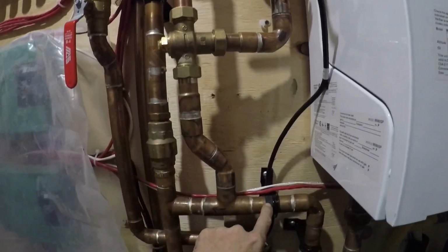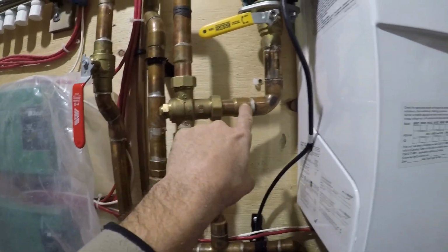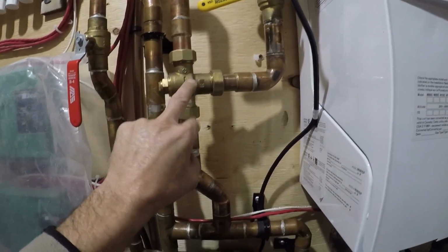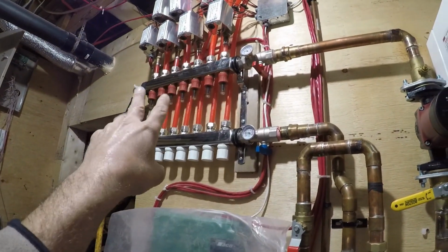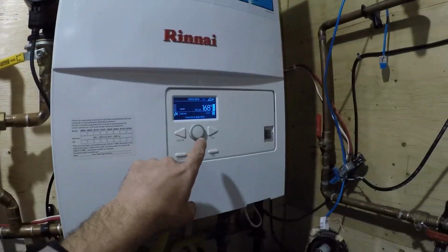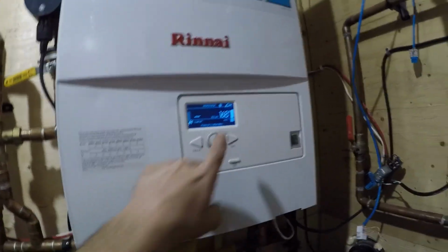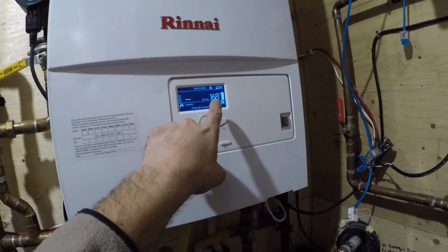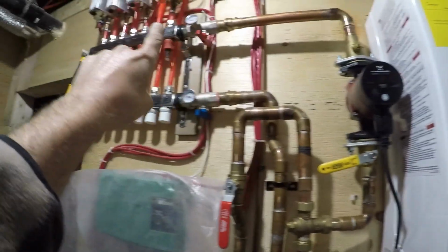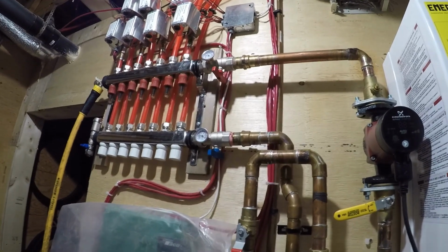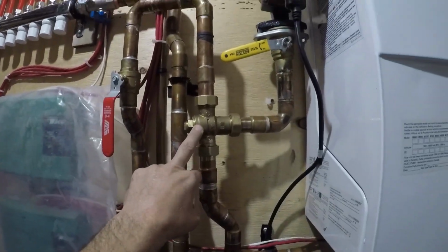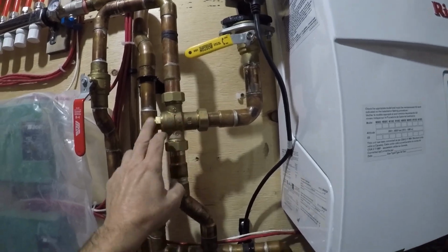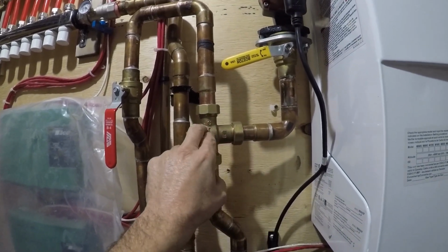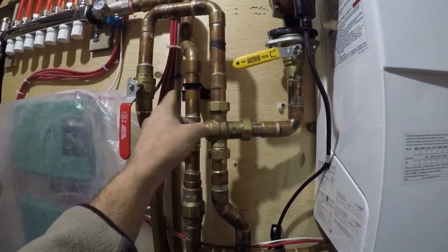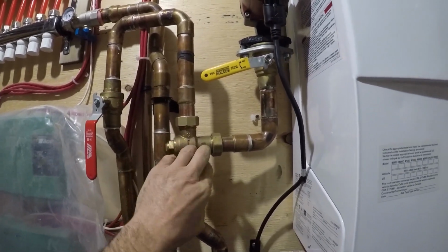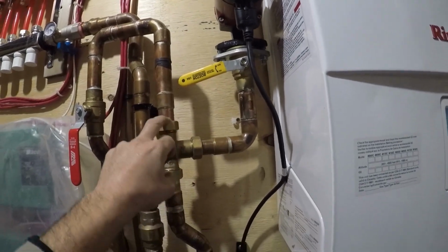The way this valve works, the hot water that comes from the boiler comes up through here and then goes out here. But you can regulate the temperature of the water going through the system, because right now the boiler is heating water to 168 degrees, and this is based on the temperature outside. So this one changes, but you want the water going through the radiant heat to be about 120, 130, somewhere around there. So the hot water comes through here, you can set the temperature of the water coming through the valve, and it regulates that by drawing cold water in to make sure it's at that 120, 130, whatever we set it at.